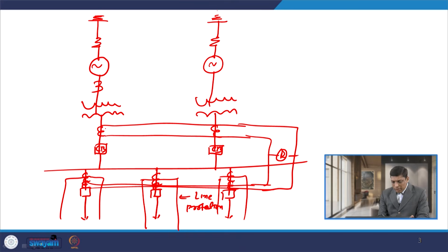Similarly, if I do it for the transformer protection zone, then the transformer protection zone has to be overlapped with the bus bar protection zone. So, I have to put the CT on the bottom side of the bus bar protection zone CT. So, I put it here and then I connect the transformer relay somewhere here. So, this is nothing but my transformer protection zone, which is overlapped with my bus bar protection zone. Same way we can do on this side also, we have to overlap these two zones on this side and we put the relay here.